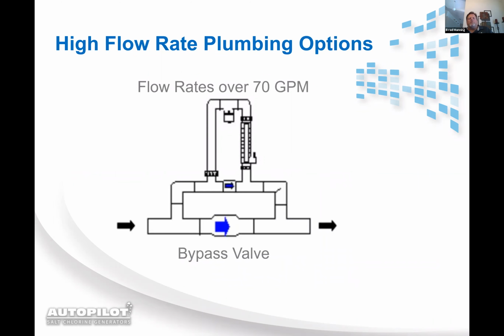This is a bypass manifold that you need to build if the flow rate is going to exceed 70 gallons per minute. And on a commercial application, that is more common than anywhere else. So, I don't want to say it's mandatory, but it's almost mandatory on every commercial application.